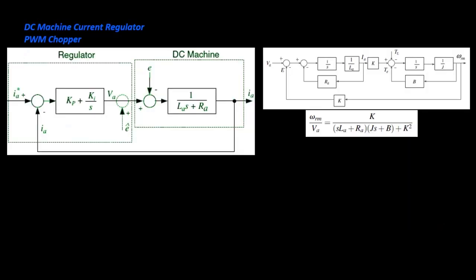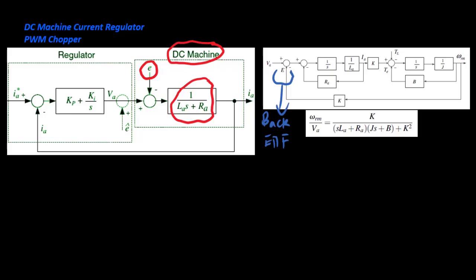If the inertia of the machine and load is large enough to consider back EMF as constant in the design of the current regulator, then the machine can be modeled as a simple RL load with constant disturbance voltage E. If the back EMF voltage can be estimated from the speed of the machine and back EMF is constant, then by feedforward compensation the disturbance due to back EMF can be rejected perfectly.